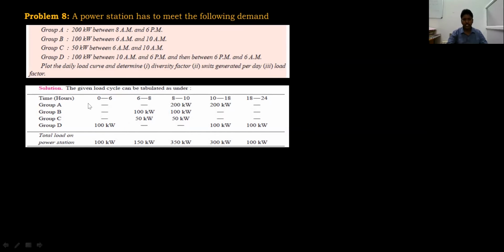Based on your flexibility, you can divide and note the total loads. Here during 0 to 6 hours, night 12 to morning 6, what are the loads present? You see, this is not present during that slot, this is not present, this is not present, and this one, 10 a.m. to 6 p.m., is not present in that slot. Between 12 midnight to 6 a.m., definitely this load is there. Therefore, out of these 4 categories, Group D is only there between 0 to 6. So I have to mention here 100 kilowatts.